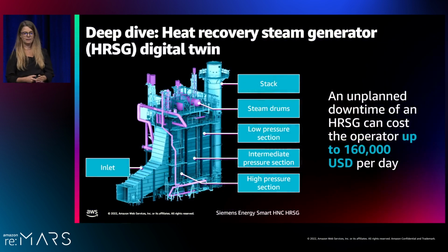So let's look at the heat recovery steam generator. A HRSG, when you look at it, it looks nice, but it's basically a monster. It's really high engineering - it has thousands and thousands of tubes that run through this building, and the building is high, around a 12-floor building, so roughly 30 meters in height that this HRSG consists of. And believe me, you don't want to be around when one of these over 1,000 tubes breaks.